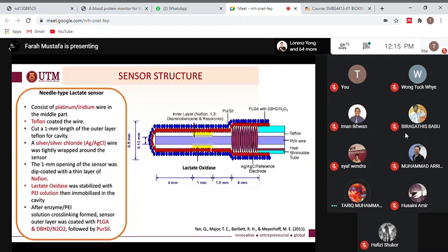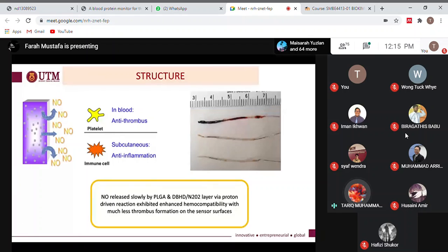So next. Okay, now for the structure, as I have mentioned just now, the layer of the PLGA and the DBHD N2O2 is actually providing biocompatibility to the sensor, because when the layer reacts, especially with moisture, or in this case blood, then it will slowly release nitric oxide. And this nitric oxide is useful because it is a thrombosis inhibitor, where it can prevent blood from forming a clot on the sensor itself, which can interfere with the accuracy of the sensor.